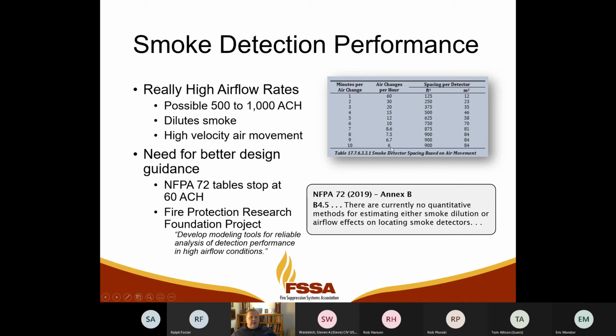Most comfort cooling, like in your commercial office buildings, we're running about 6 air changes per hour, and the code says, hey, smoke detector spacing is 900 square foot per detector, so 30 by 30 spacing on your detectors. But as the air change rate goes up, we dilute the smoke faster, so the spacing of the detectors has to get tighter and tighter.